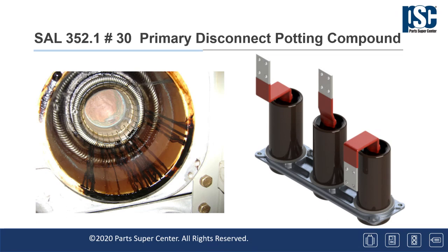The black pitch material was replaced with a modern solid dielectric epoxy starting in 1994 due to oil migration out of the black pitch and dripping down onto the circuit breaker bushings. The picture on the left is representative of this condition and is a view looking up into the bottom of the primary disconnect where the bushing on the circuit breaker would plug in. Operating experience has shown the oil tends to migrate out of the pitch more frequently on circuit breakers that operate near their continuous current nameplate rating, that operate in high ambient temperatures, and after 40 years or more of service.